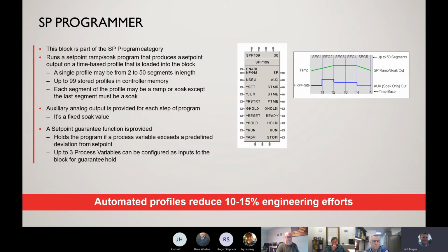The control display on the HC900 also has a very nice display that shows you the process variable versus the set point of your set point program profile, and it will actually pre-plot that set point profile for the entire program. This allows the operator to look at the display and verify that they have the right profile loaded before they go ahead and run it. That tool is pretty powerful, and like I said, for somebody to build a display like that would take many engineering hours. But with the HC900 display, that's out of the box and ready to go. All you have to do is import the tags with a small amount of configuration and you're up and running.